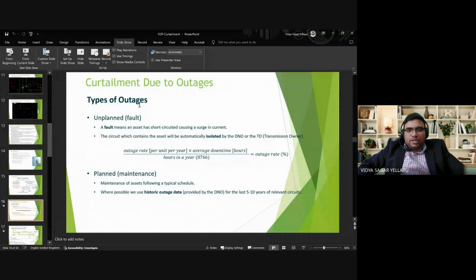Those outages may be unplanned outages, which are due to faults. If a fault happens, no one can control that event, and it happens. If there is an unplanned outage, then that leads to 100% curtailment for the project. The curtailment rate or outage rate in percentage is given by outage rate per unit per year multiplied by average downtime, divided by hours in a year. It is to be 8760, but considering the leap year in one of the 5 years, the average is 8766.